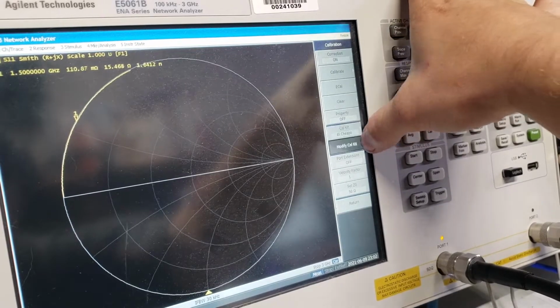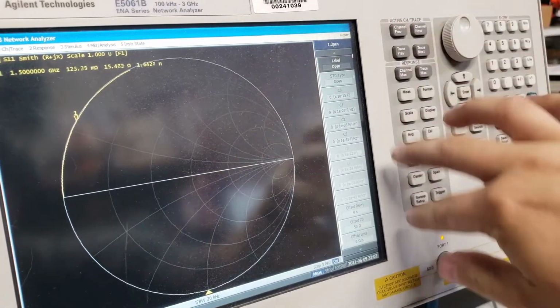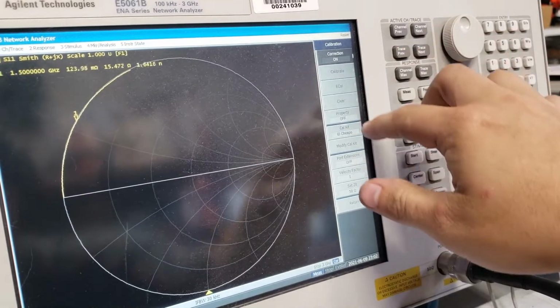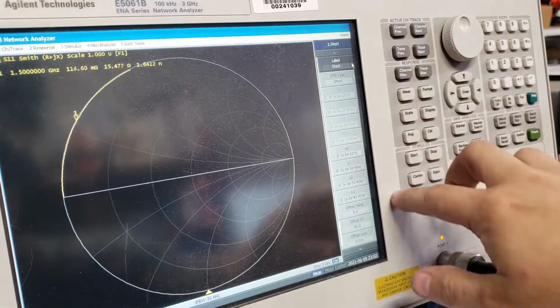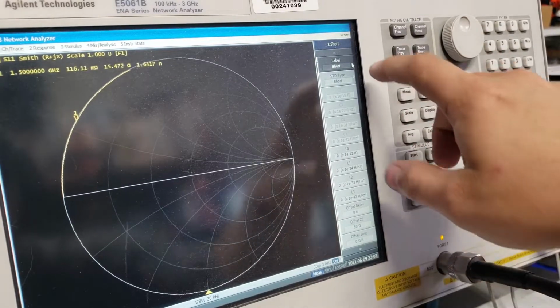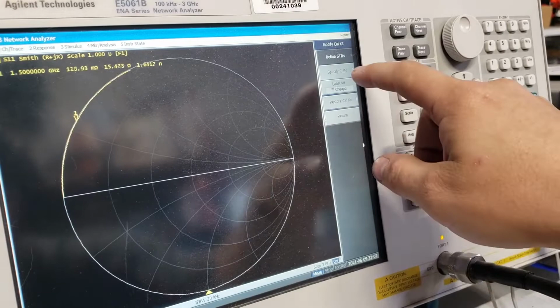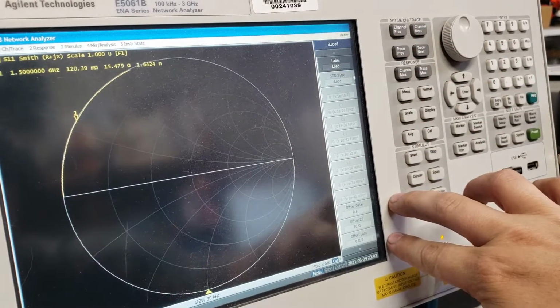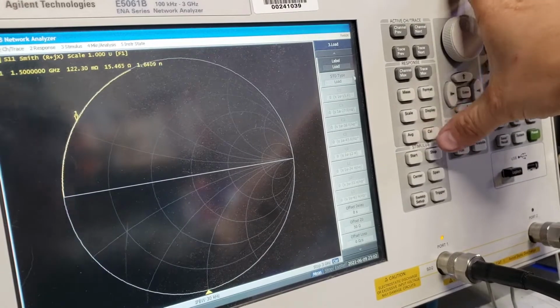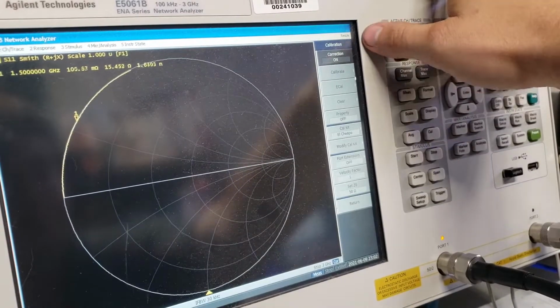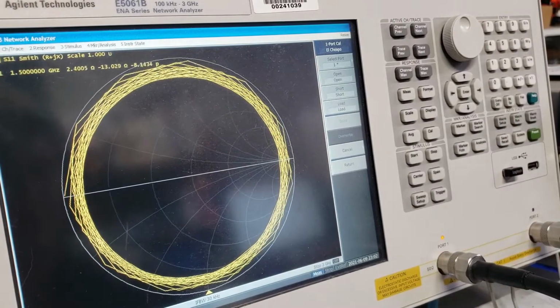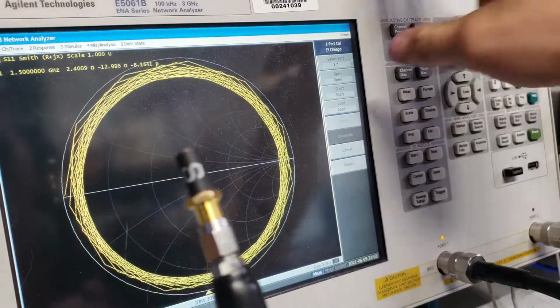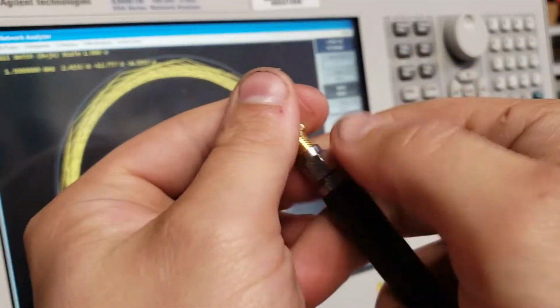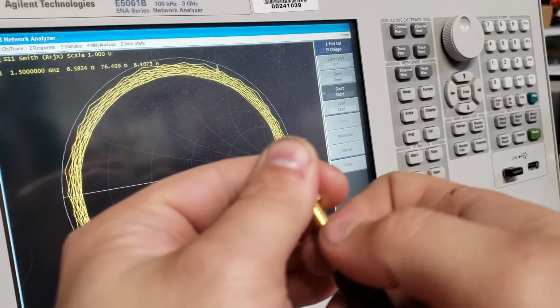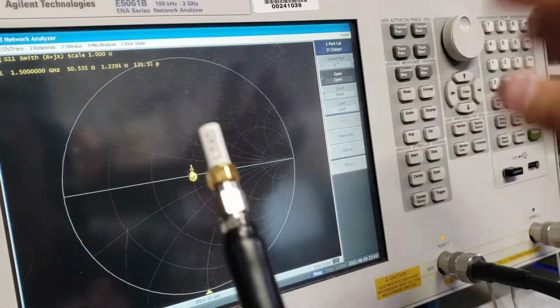So how do you fix this? Well, you just define a custom calibration kit on your professional VNA that assumes the standards that you're using are absolutely perfect. And this will give you measurements that are basically the same as what you can get on the front panel of the NanoVNA V2, or very close to it. And while they might not be as close to the reality of what the true measurement is, they'll at least agree with what you're measuring on the other device. So here I'll repeat the calibration procedure real quick with the perfect calibration kit defined in the E5061B VNA. And then we'll take a look at our standards and how they measure and see if they pass our sanity test that we typically use for NanoVNA V2 measurements.